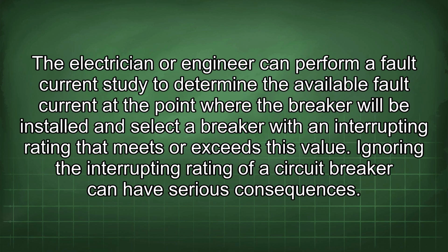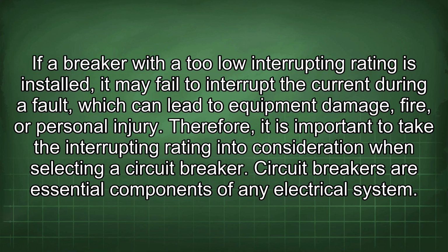The electrician or engineer can perform a fault current study to determine the available fault current at the point where the breaker will be installed and select a breaker with an interrupting rating that meets or exceeds this value. Ignoring the interrupting rating of a circuit breaker can have serious consequences. If a breaker with a too low interrupting rating is installed, it may fail to interrupt the current during a fault, which can lead to equipment damage, fire, or personal injury. Therefore, it is important to take the interrupting rating into consideration when selecting a circuit breaker.